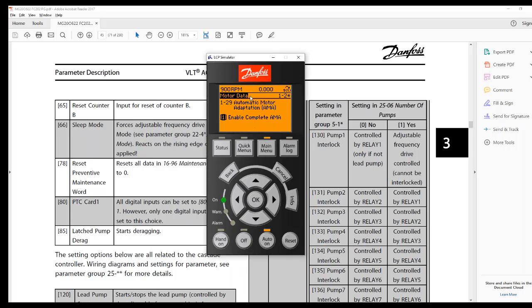It actually, when it's doing the tuning, it makes the current signature ring, and it does different carrier frequencies to figure out when that ringing goes away, and that's the number. So think of it as like a digibridge or a millihenry kind of metering that it's doing to learn what the reactance is. But if that cable has too much capacitance, or there's other, let's say, noise or interference happening, and it can't get a steady signal, then this AMA will fail.